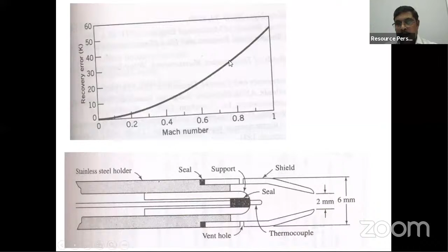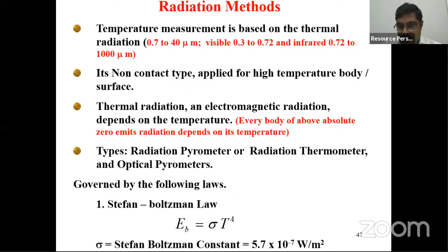The last method is the radiation method, where temperature is measured based on radiation, which is an electromagnetic propagation. By focusing the radiation emitted from the body onto a black body or a photon detector, you can measure the temperature using the fundamental law of radiation. Here we have the radiation pyrometer or optical pyrometer, bolometer, and IR thermometer, among several other versions we will see.